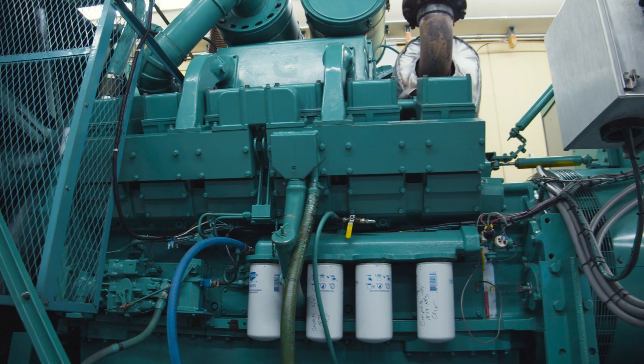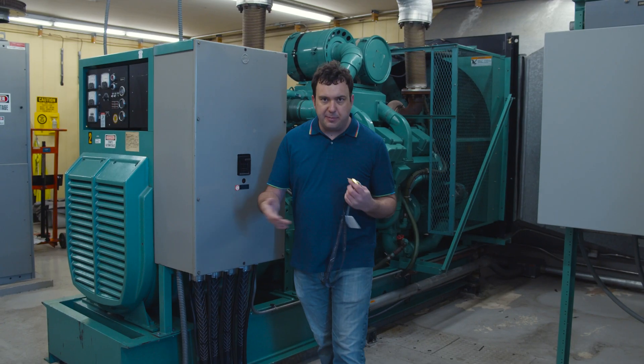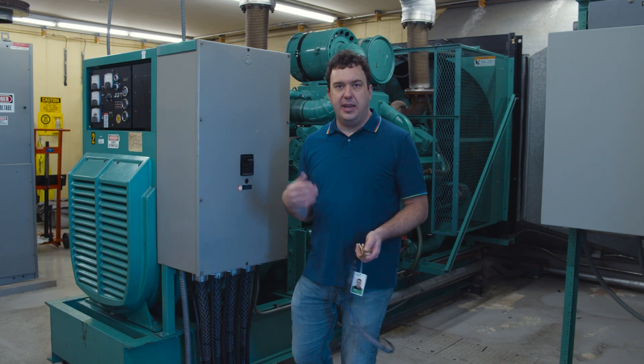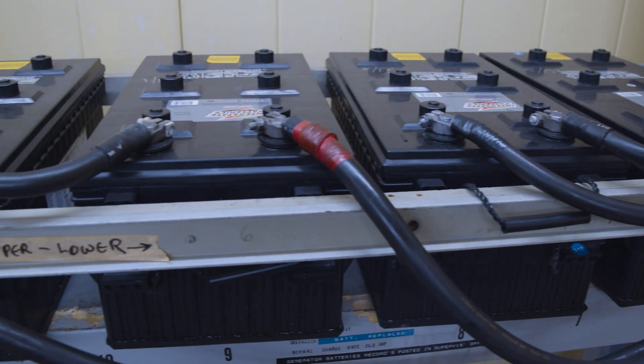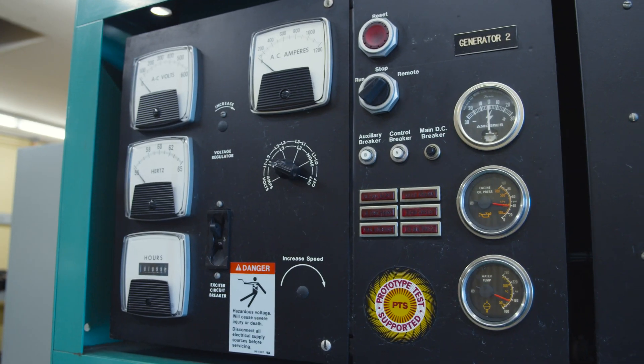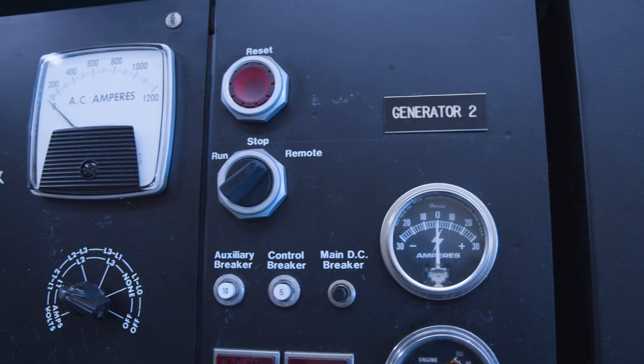This site would only require one generator in winter; in the summer it requires two out of the four to be working to carry the site. That's part of our defense-in-depth to outages and how we keep the service running even when something fails. We don't share battery strings or anything across generators — they all have to fail independently — because generators can and do fail, which is why there are always multiple generators available at our important sites.